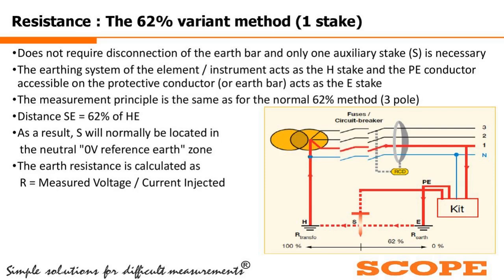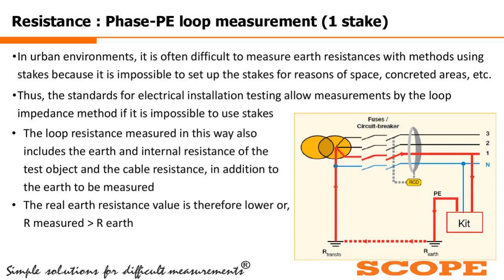Now this 62% has not come just like that. People have done a lot of study, and then they found out the 62% zone is the safe zone, or the ideal zone, to do the measurement. So, if the length of HE is 100 meters, then the voltage lead should be connected at a distance of 62 meters from the instrument. The earth resistance is calculated as V equals IR, or R equals measured voltage divided by current injected. So, the classical Ohm's law formula is used in the same fashion in this measurement.